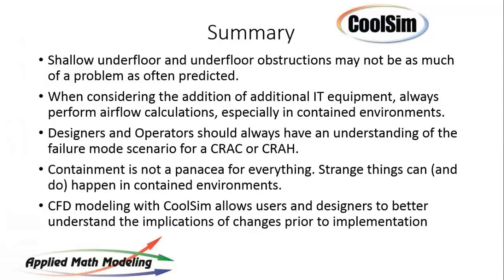We were able to show you today that you can be very close and still do okay. In other words, we were right about where we needed to be with all units running and still able to provide an n+1 situation. But you're not going to know unless you test it or model it. And this is to a point you've made a couple of times, Lauren. Operators need to understand the failure mode scenario. Do you want to speak to that one a little bit?